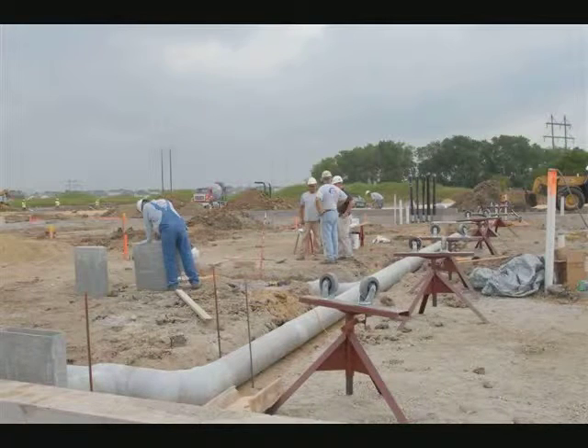We tried to prefab as much above ground as possible, tried to eliminate as many joints down in the trenches as we could. We had a telehandler on site, so we were able to put two 20-foot lengths together into 40-foot lengths. We took precautions when we lifted them after the joints were made up, on how we raised and set them.